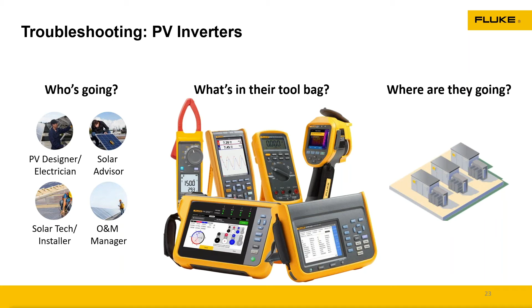One site I went to in Georgia, the inverter kept tripping out. They went through and investigated the system. Come to find out, it was actually harmonics and transient issues coming from the utility side, and it would go back to the inverter. The inverter recognized it and tripped out. We had to use a power quality unit to go in and validate those numbers and see what that looked like, to then go back to the utility to say this was an issue. Again, great tool to be able to analyze and troubleshoot that system.